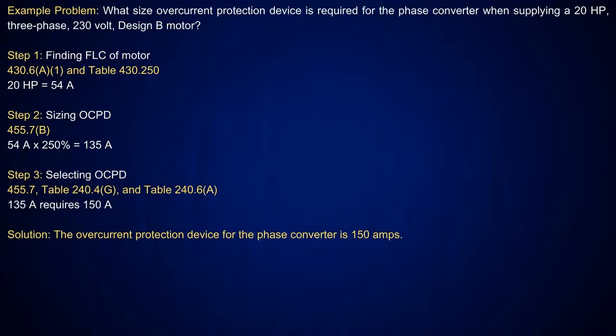Okay. Now, the next thing we're going to do to get you ready for next week in the homework, the first one we're going to do here is we're going to be looking at sizing the overcurrent protection device where I have a phase converter. So in this case, I've got a 20 horsepower, three-phase, 230 volt design B motor. Now, like I said, when you're sizing the overcurrent device, 430.6A1 will tell you to go look at the tables. In this case, since it's a three-phase, we're looking at table 430.250. And if I pick up my 230 volts and I come down, pick up 20 horsepower, it's going to tell you it's good for 54 amps.